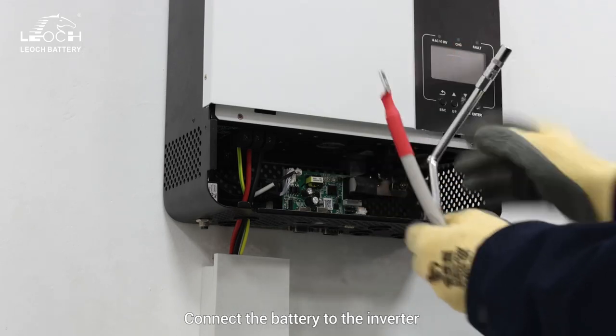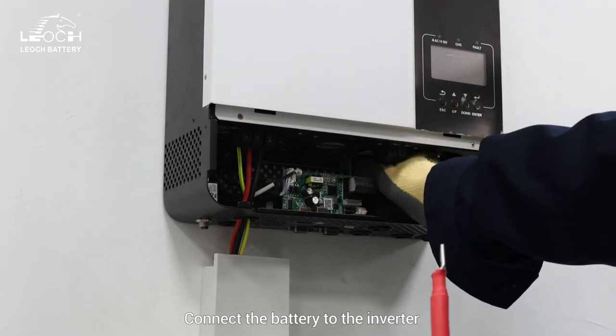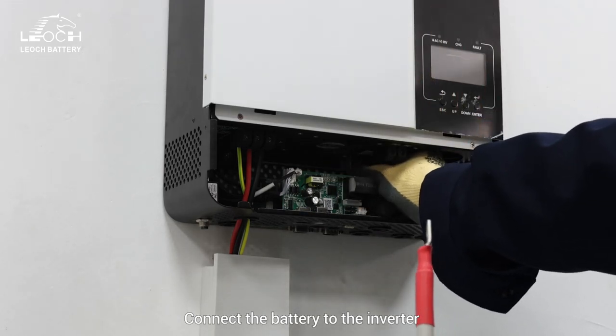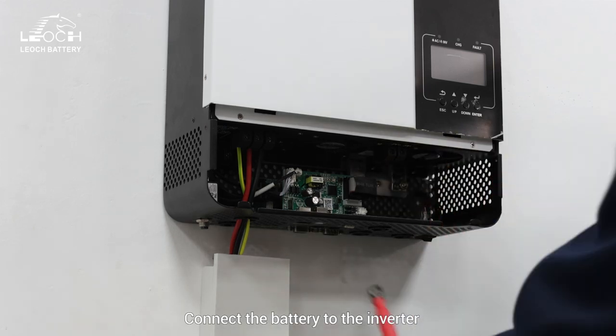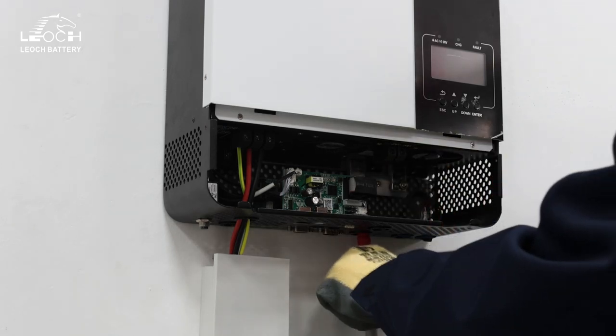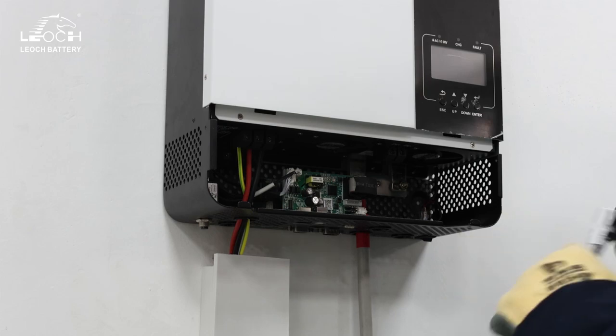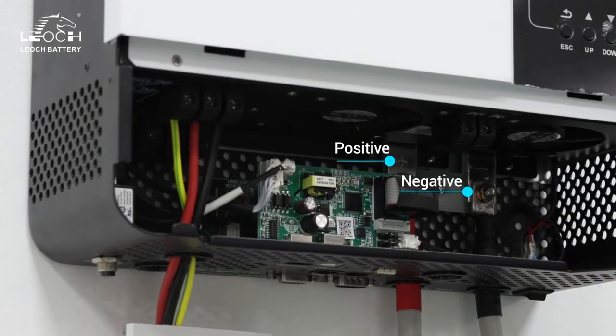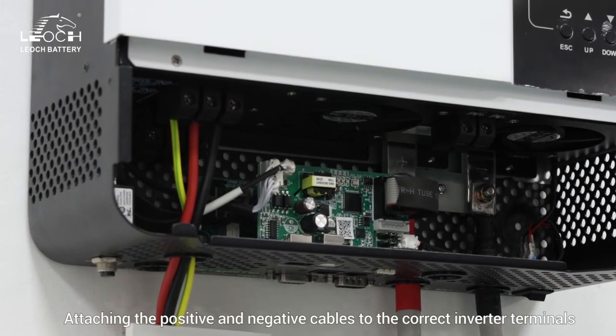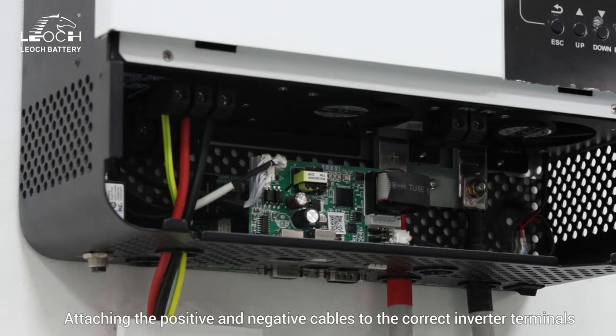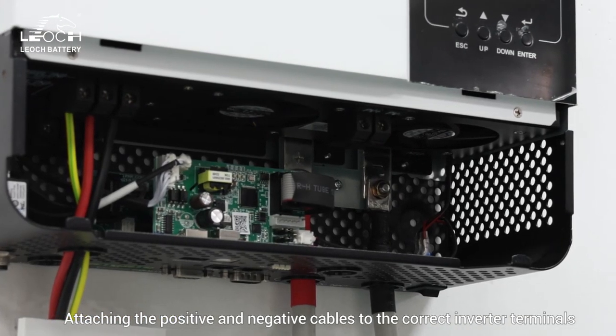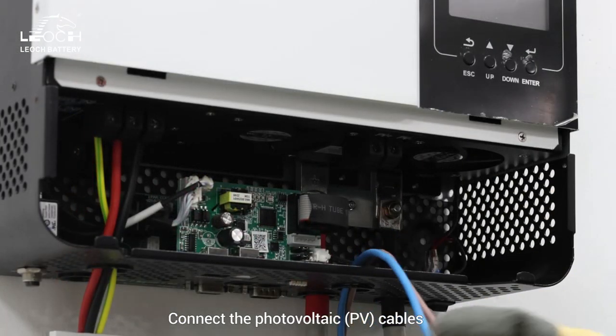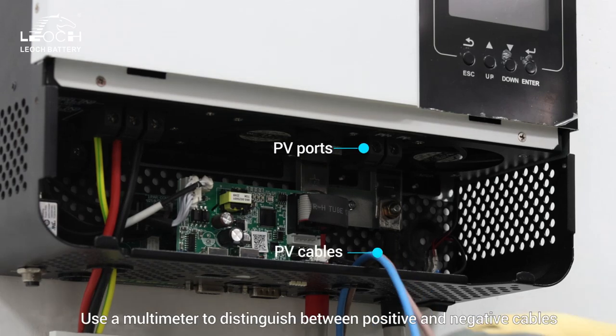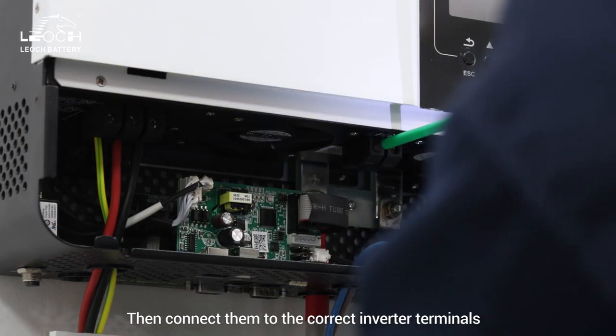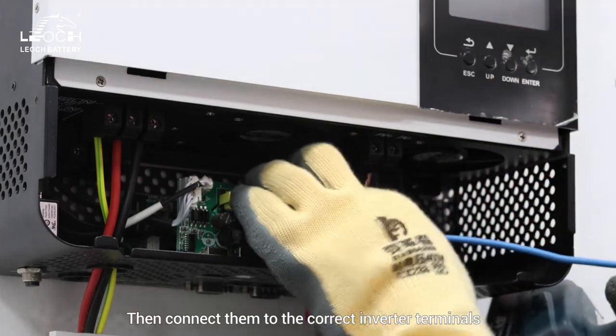Connect the battery to the inverter, attaching the positive and negative cables to the correct inverter terminals. Connect the PV cables. Use a multimeter to distinguish between positive and negative cables. Then connect them to the correct inverter terminals.